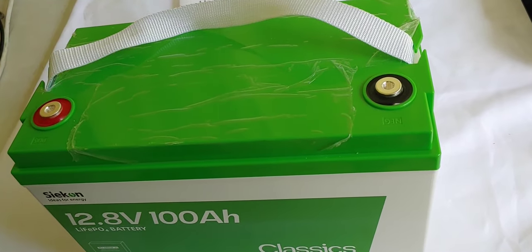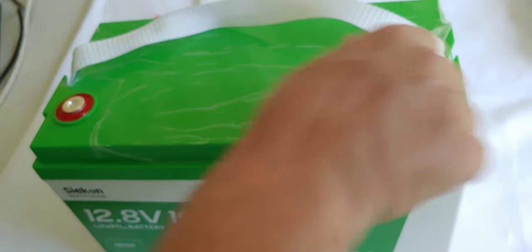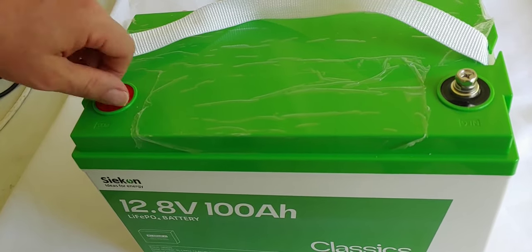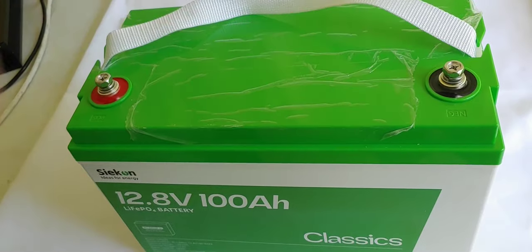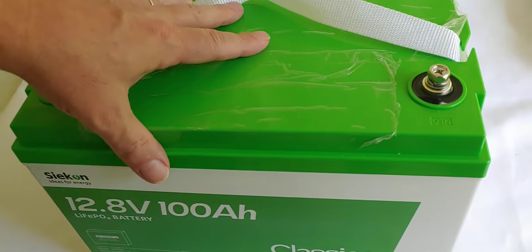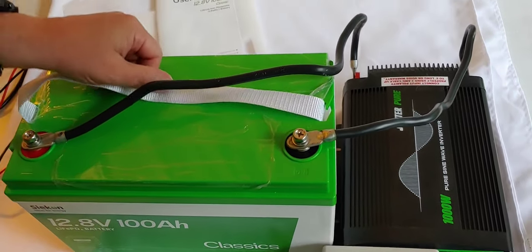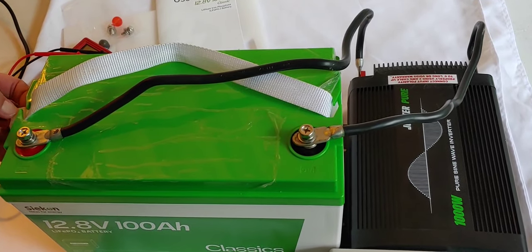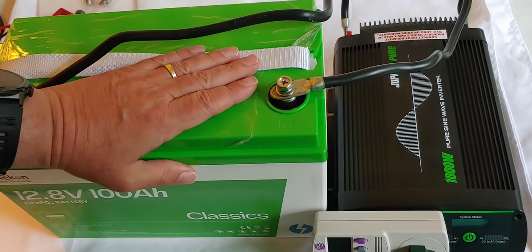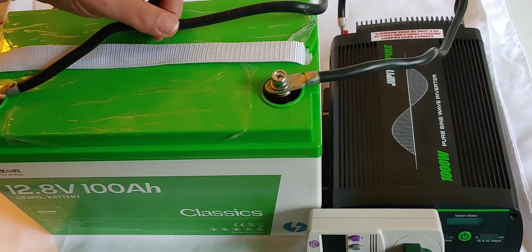Then I'm going to take it in and do a capacity test and test it on the computers. When I'm finished with that I'll let you know the results, and then we will come back here and do my fan test, which is the real test for all these batteries. We have charged the battery all the way up, took it in the lab and tested it — it actually did 105 amp hours, so that's pretty good.